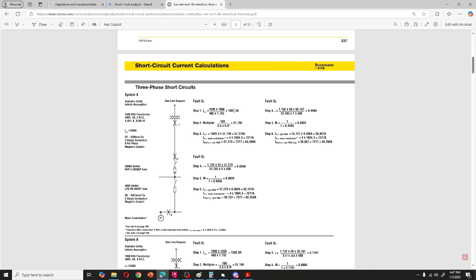That's 1804.3 amperes. Then for the multiplier, take 100 divided by 3.5, times 0.9 - that's constant. So that's 31.746. Then multiply that by your ILL, or line to line, and you will have approximately 57,279.